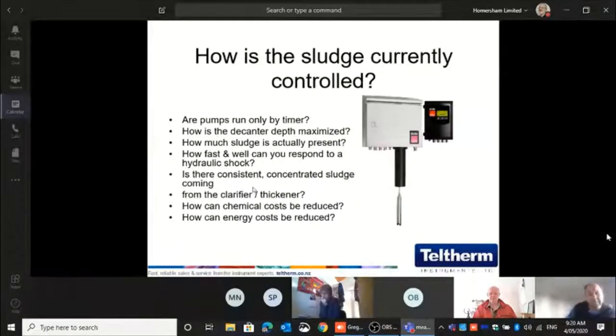The problem at the moment is that most people use the pumps and they run only on timer. So you don't really know if you're pumping out water or actually sludge. The unit is not very cheap, because we're looking at around $18,000 for the complete system. But you can reduce your cost very rapidly, mainly energy and chemical costs.